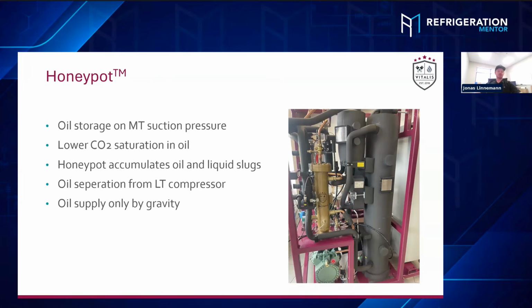And we do have some good side effects as this sits on the suction side. In case we would get liquid slugs back from the medium temp evaporators, it would separate that liquid in that separator as well. You don't want to have that liquid in there mixing with the oil, but it's still much better than just slugging it back to the compressor. And on the other hand, we basically route the low temp discharge through that vessel as well. So most of the low temp oil carryover gets separated in that vessel already. So that's pretty handy and an easy system, because you want to have the system as easy and safe as possible.